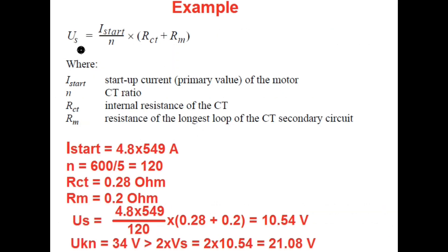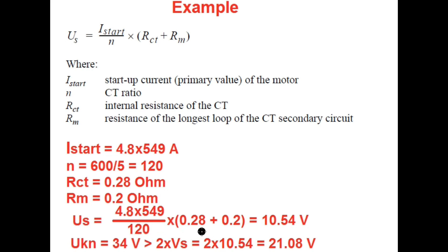Calculating the stabilizing voltage: Us = (Istart / n) × (RCT + Rm). Here RCT = 0.28 Ω and Rm = 0.2 Ω. Starting current = 4.8 × 549 A, CT ratio n = 600/5 = 120. So Us = (4.8 × 549 / 120) × (0.28 + 0.2) = 10.54 V.